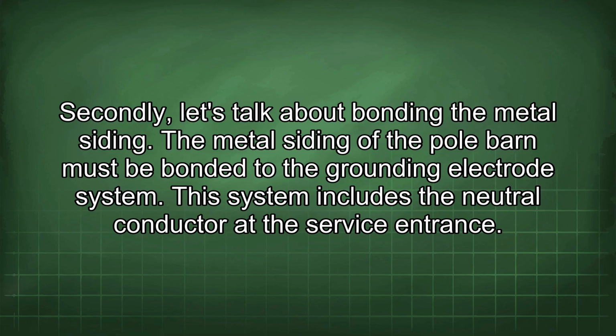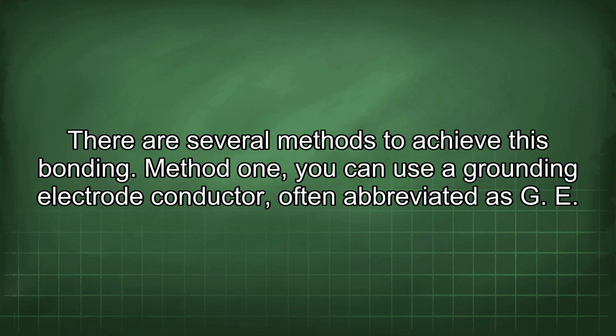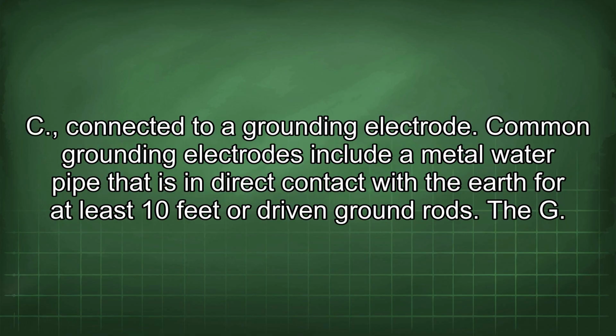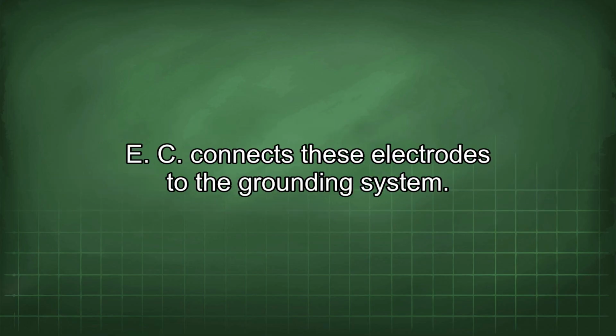Secondly, let's talk about bonding the metal siding. The metal siding of the pole barn must be bonded to the grounding electrode system. This system includes the neutral conductor at the service entrance. There are several methods to achieve this bonding. Method 1. You can use a grounding electrode conductor, often abbreviated as GEC, connected to a grounding electrode. Common grounding electrodes include a metal water pipe that is in direct contact with the earth for at least 10 feet or driven ground rods. A GEC connects these electrodes to the grounding system.